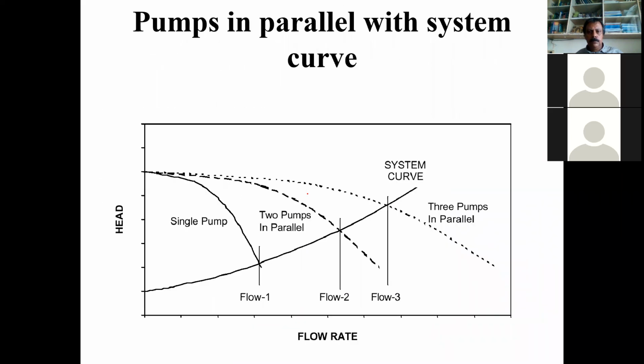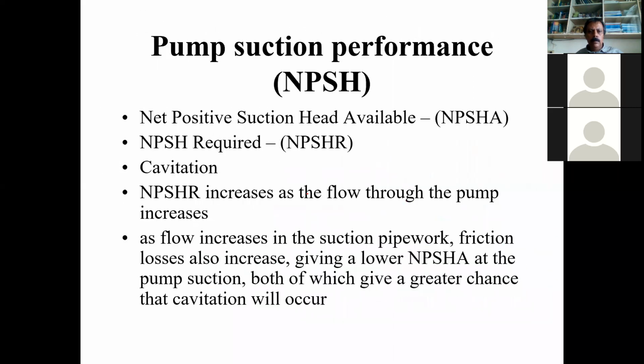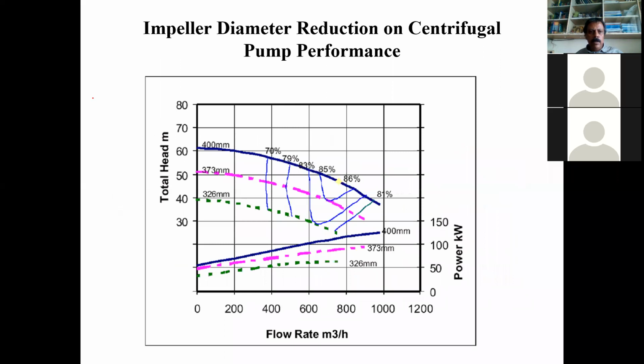we've already seen that your power is proportional to the cube of the speed. So if you reduce the speed by 20%, the power will come down by 50%. This is the affinity law. The flow is proportional to the speed, head is proportional to the square of the speed, and power is proportional to the cube of the speed.